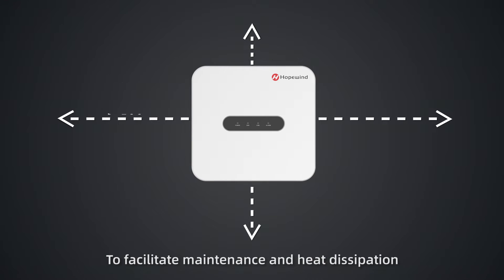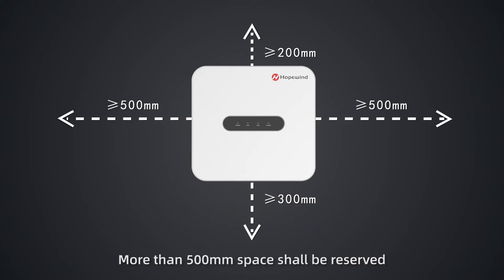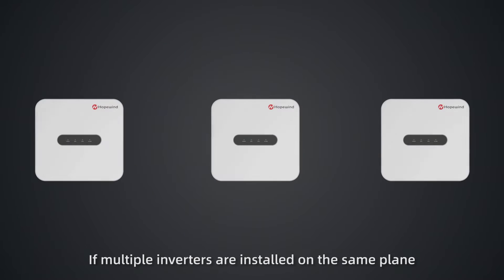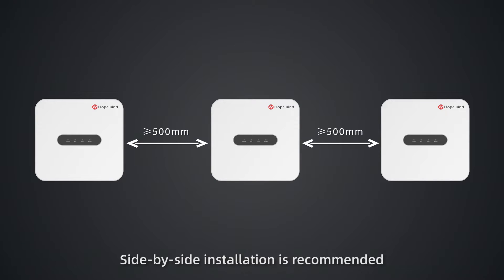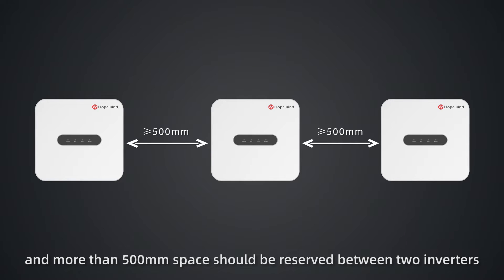To facilitate maintenance and heat dissipation, more than 500 mm space shall be reserved on the left and right of the inverter, and at least 200 mm space above and 300 mm space below the inverter. If multiple inverters are installed on the same plane, side-by-side installation is recommended, and more than 500 mm space should be reserved between two inverters.